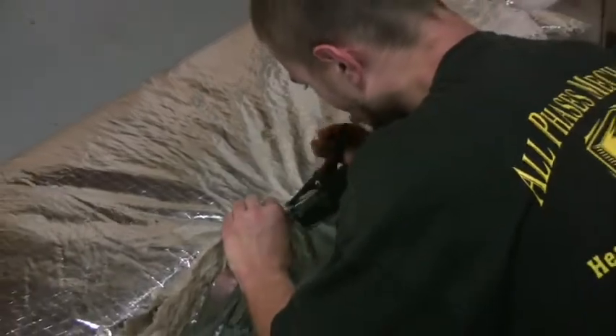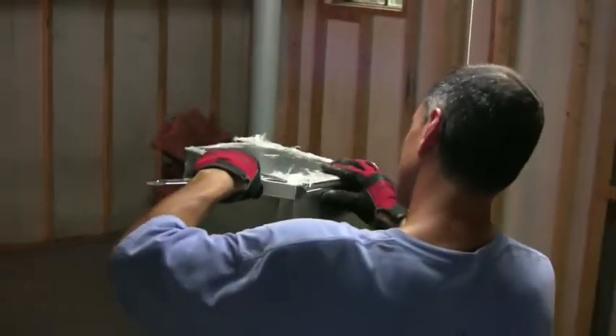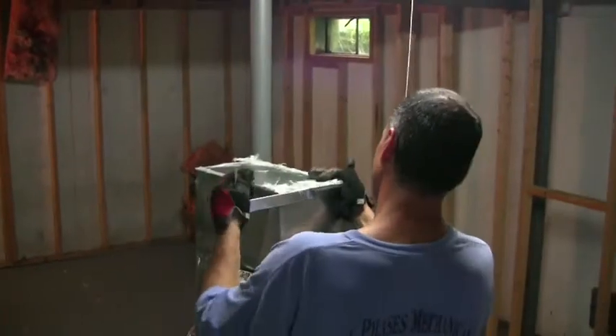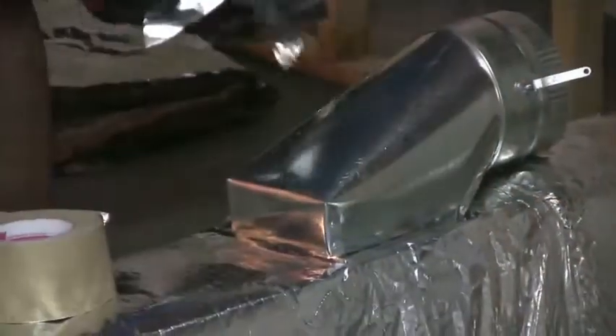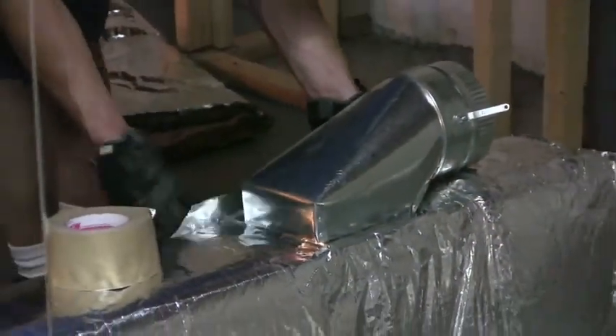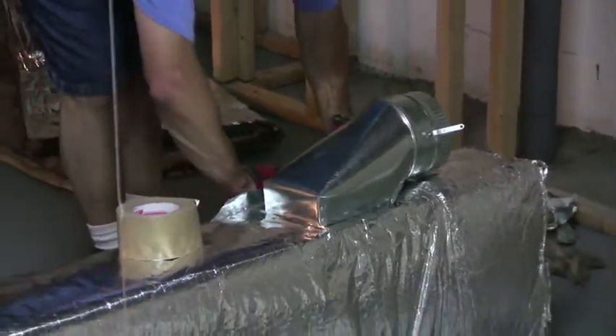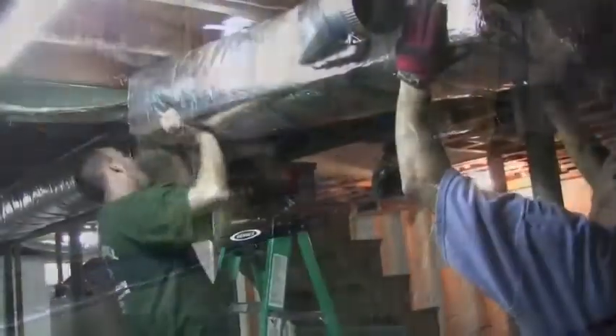Get it done right. There's Jeff insulating ductwork with 2-inch FSK, which is standard. A lot of guys try using bubble wrap and don't do the vapor barrier correctly to get the right R-value. As you can see, most of our takeoffs on ductwork have dampers in them.